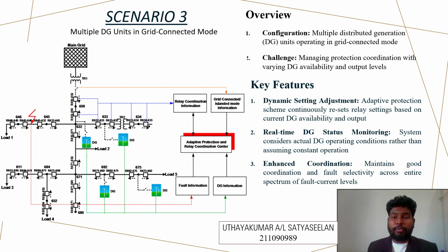So for the scenario 3, it's about the multiple distributed generation units in grid connected mode. So for the overview, it's a configuration about multiple distributed DG units connected in grid connected mode. So what are the key features? The key features discussed here is the dynamic setting adjustments, adaptive protection scheme continuously resets relay setting based on the current distributed generation availability at that time, and also the output, followed by the real time distributed generation operation condition rather than assuming constant operation.